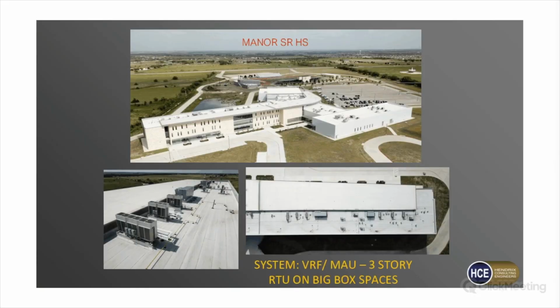Here you'll see a school - this is a 3-story classroom wing with some big box spaces that are double high, and I don't think there are any single-story spaces on this. Along the left-hand side of the boomerang, as we like to call it, that 3-story classroom wing, the district chose to go with VRF. This worked pretty well because we're able to compile all the heat rejection equipment - on the lower left you'll see the condensing units on the roof. The footprint was favorable because as you get taller, you run out of roof space. Behind a couple of those heat rejection units are heat recovery units that make up air, so they had dedicated outside air. We coordinated chases to get the outside air down to all 3 floors, but they just had indoor air handlers that served each classroom.